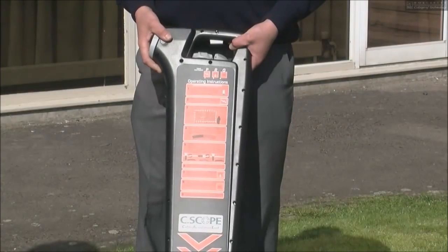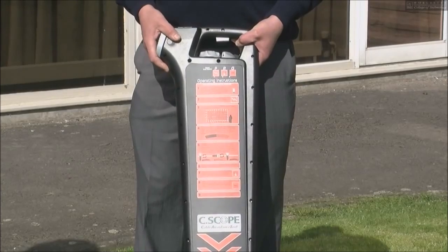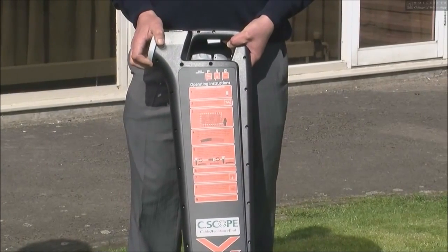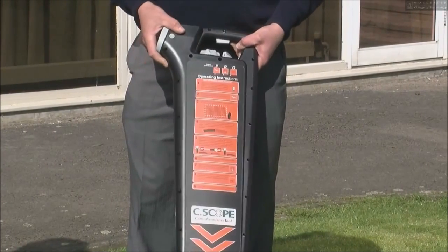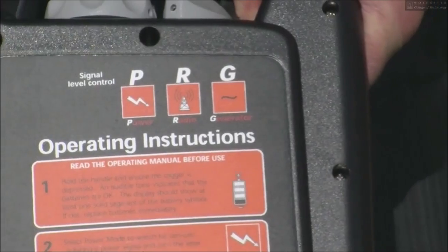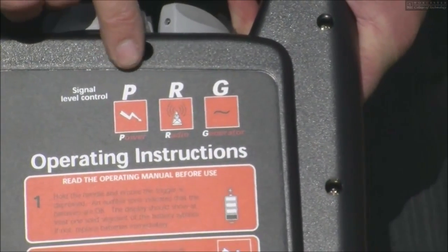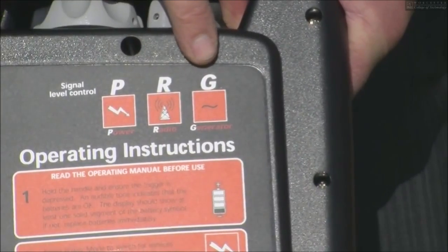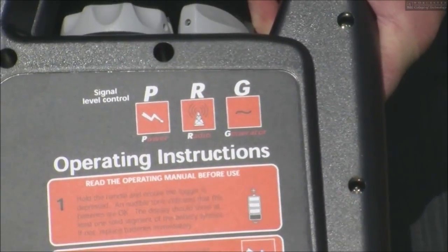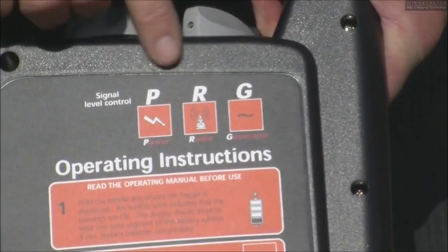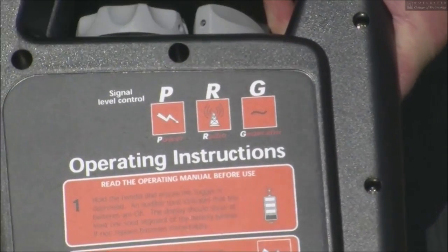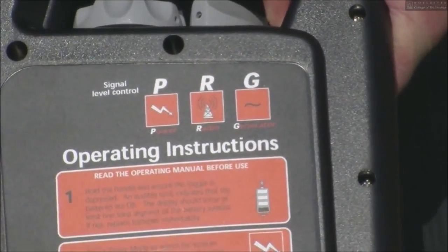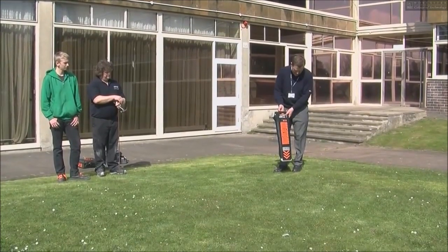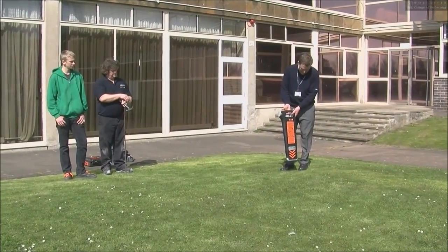Before we go driving any earth electrodes into the ground, we need to check the ground first to see if there's any buried cables, gas pipes, water pipes. So we're going to use the cable avoidance tool. These are the 3 settings we're going to use. There's the power, radio and generation. We're actually going to just use the power for this one. We can also use the radio detection to see if there's any data cables under the ground, but I very much doubt it.